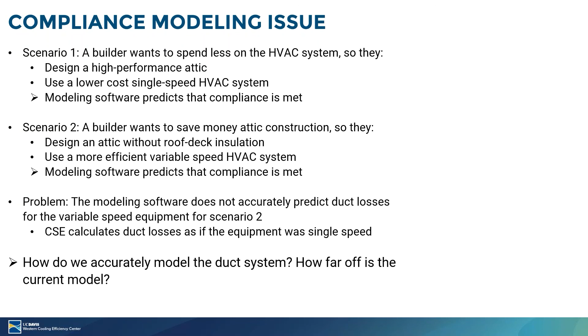CSE actually calculates duct losses as if the equipment was single speed, even if you're designing with a variable speed piece of equipment. There's just no option for the user to define that, and it's not really the software's fault. You know, technology is evolving, so now we're running into a few issues, and how do we fix them? And how do we accurately model the duct system, and how far off is the current model?